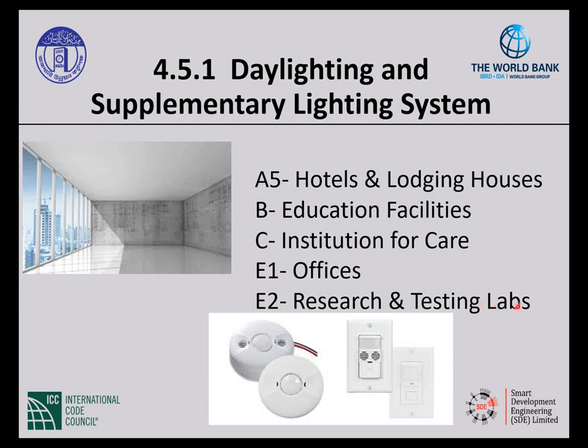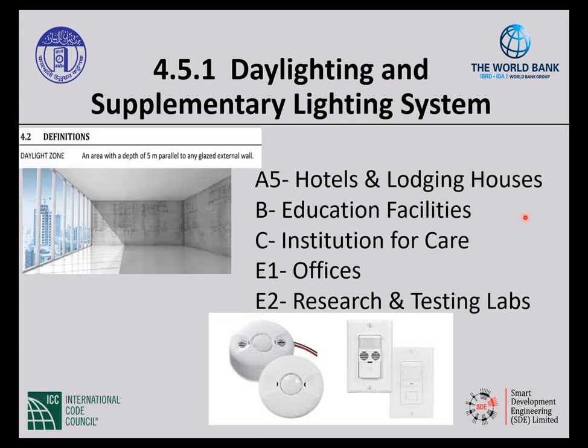Right? And so it says that the photoelectric sensor shall be located approximately half the depth of the daylit zone. Let's go to the definitions section in this code to find that a daylit zone is an area with a depth of 5 meters parallel to any glazed external wall. So we have this wall, and for 5 meters parallel to it, we have this daylight zone. We need to put our controls halfway into that zone. That's what that is telling us.